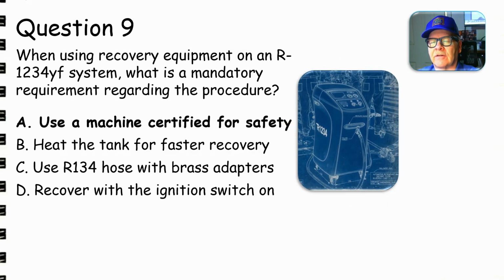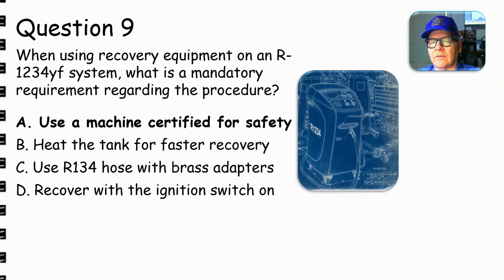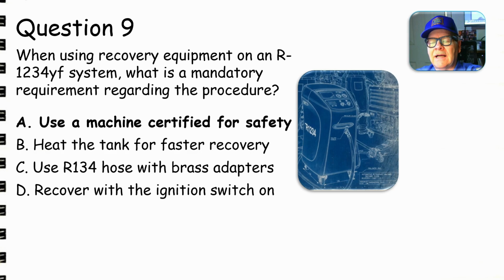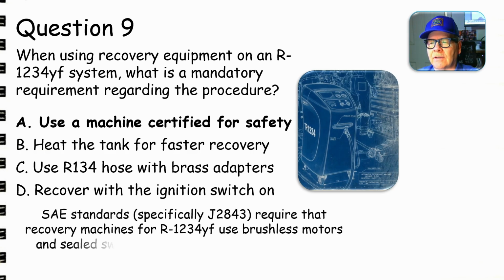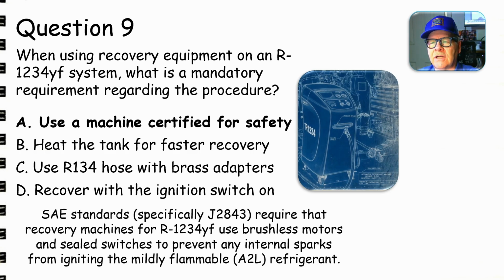Use a machine certified for safety. What the deal is here is SAE standards J2843 require recovery machines use brushless motors and sealed switches to prevent internal sparks because R1234YF is kind of flammable. Of course, R134 is too, but R1234YF is more flammable. It's an A2L refrigerant. You can look that up whenever.